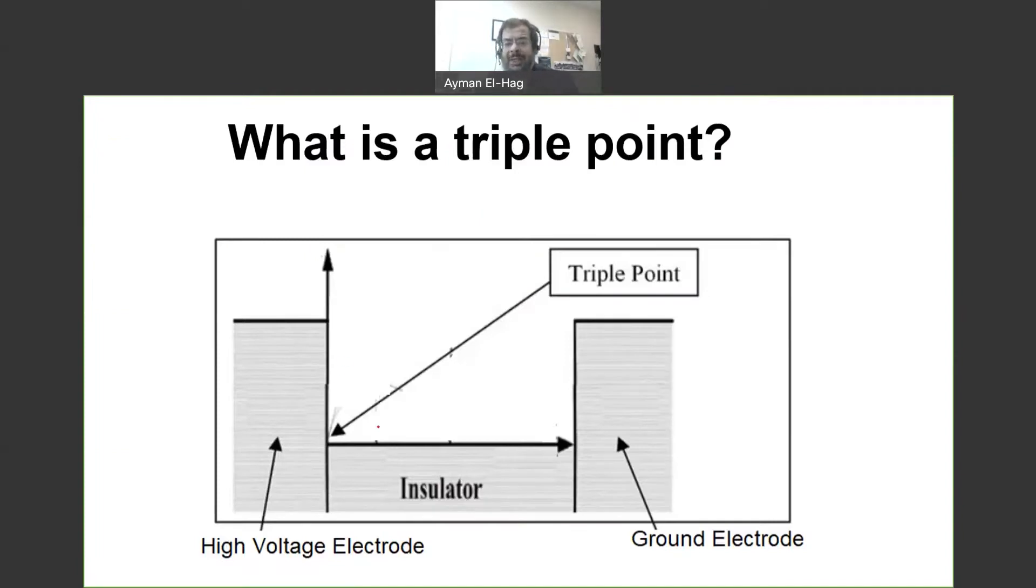Basically, a triple point is a point between three different materials, and each material will have a different dielectric constant. So, for example, here, this is a triple point where we have air, and as we know, air has a dielectric constant equal to 1. Insulated material, where epsilon r here can be between 2 to 5. And here we have a metal where we will have a very high dielectric constant. You can assume it going to infinity.